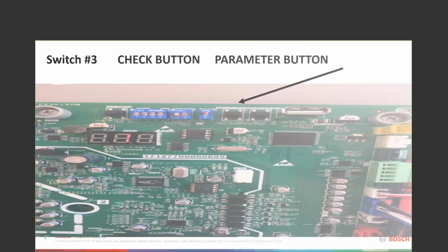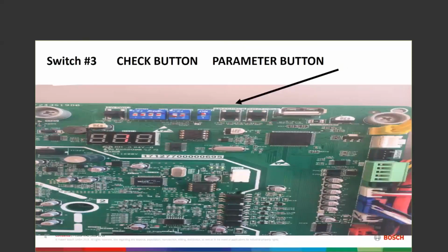And number 3, my favorite button. I tell people all the time, this is not my dad's unit, not my grandpa's unit type scenario, but this button allows me to look at what's going on, whether the system is running or not. The 1.0 had about 17 parameters on a chart that I could sit on a bucket and find the numbers for. The 2.0 has about 25. So we've added some parameters to this button, literally leaving the voltmeter and the gauges in the truck from here on out on the 2.0.